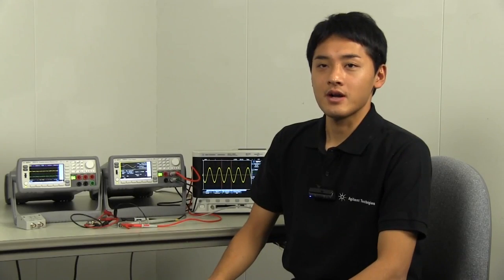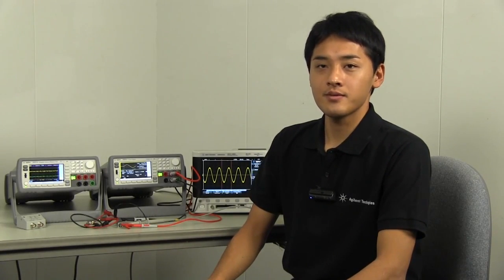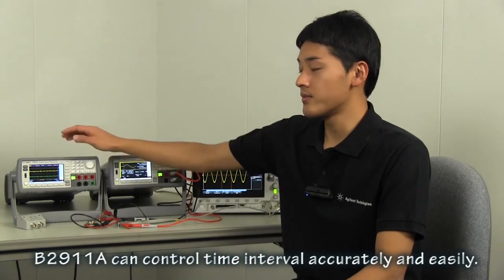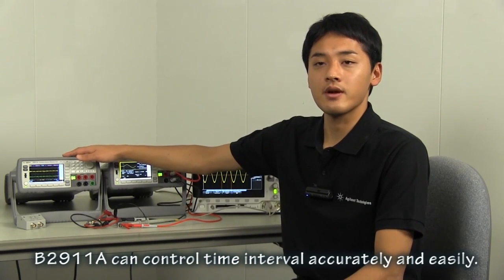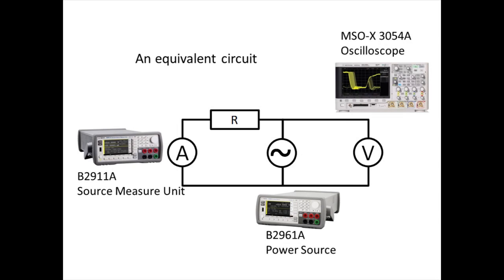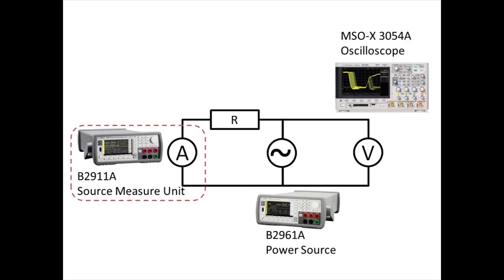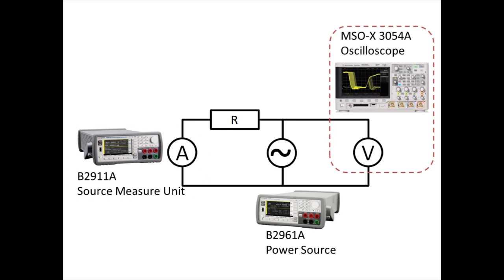When we measure current waveforms, we might have to set a specific constant time interval. We cannot control it accurately with conventional instruments. With the Agilent B2911A, we can control it easily. In this demonstration, I use these instruments: a power source as an AC voltage source, an SMU to measure current waveforms, and an oscilloscope to observe voltage waveforms.